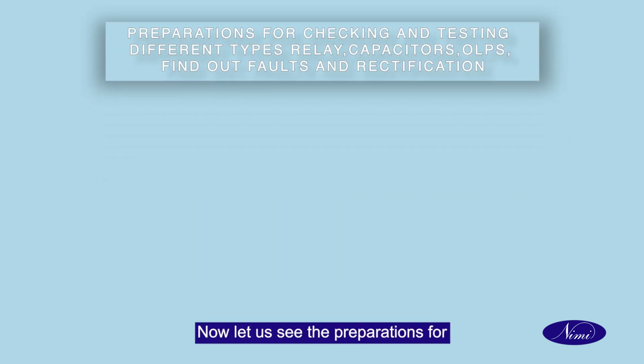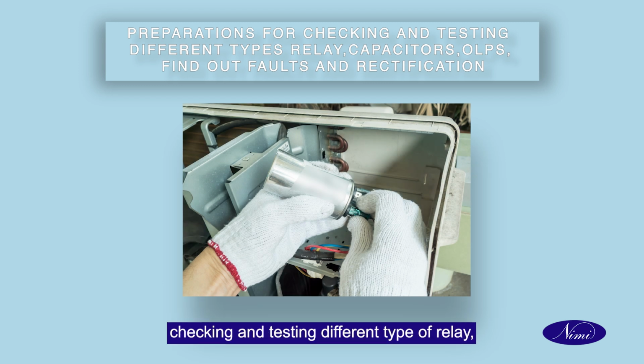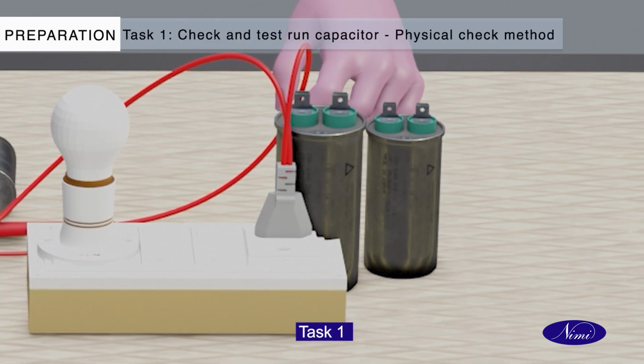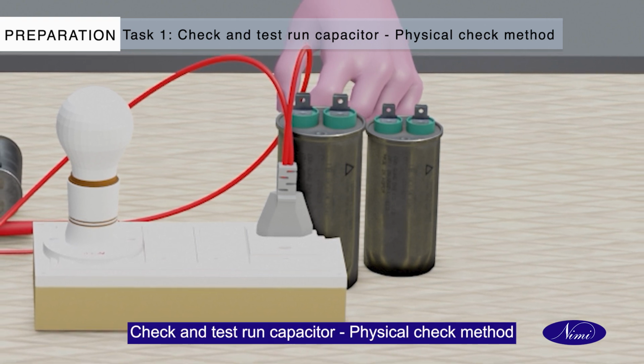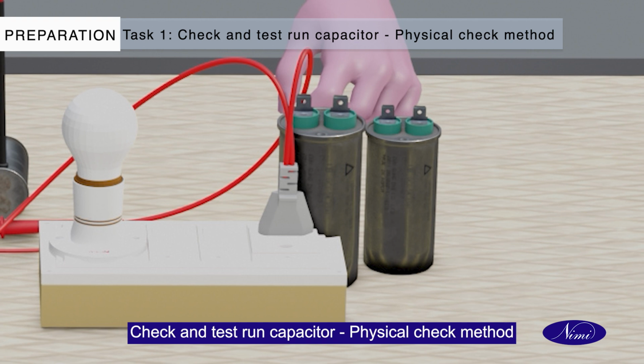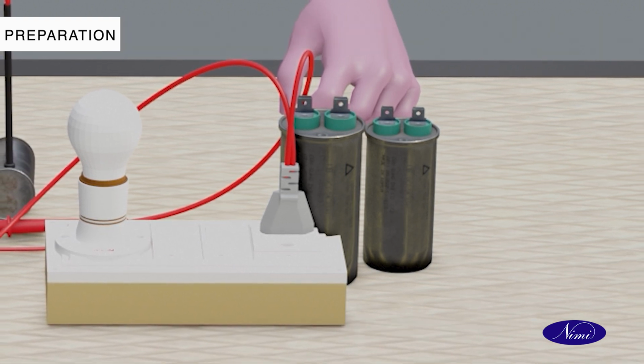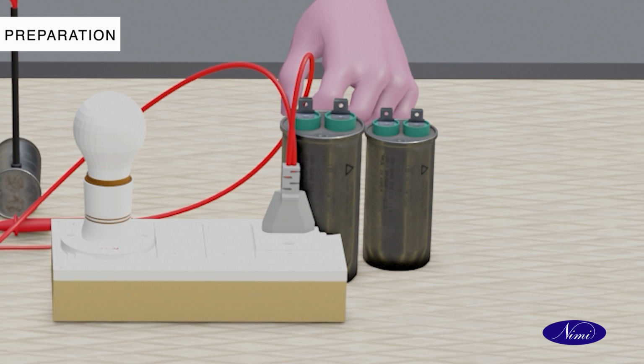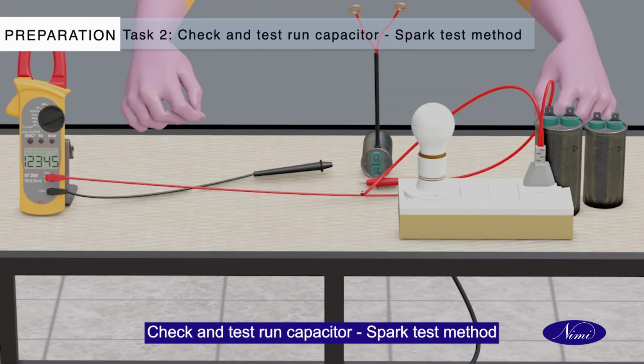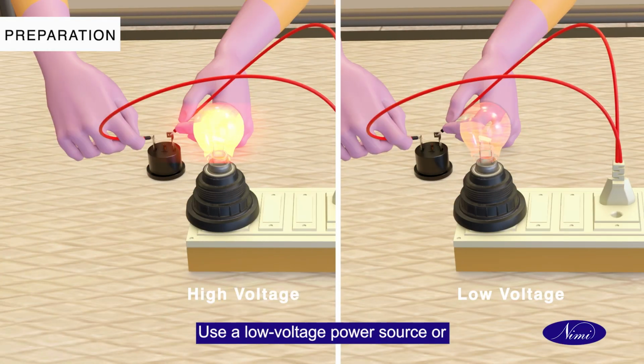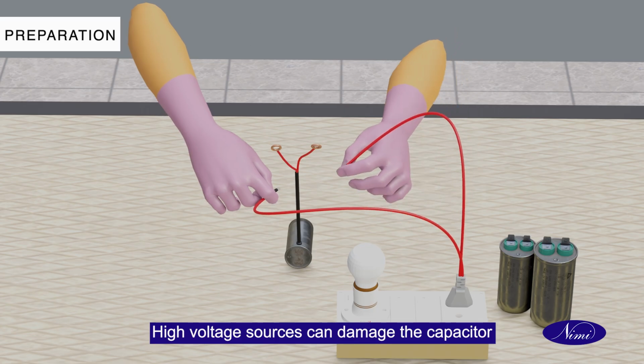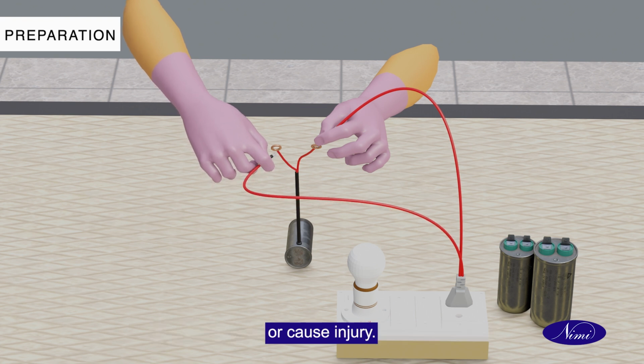Now, let us see the preparations for checking and testing different types of relays, capacitors, OLPs, finding faults and rectification. Task 1. Check and test run capacitor. Physical check method. Task 2. Check and test run capacitor. Spark test method. Use a low voltage power source or a charging tool designed for this purpose. High voltage sources can damage the capacitor or cause injury.